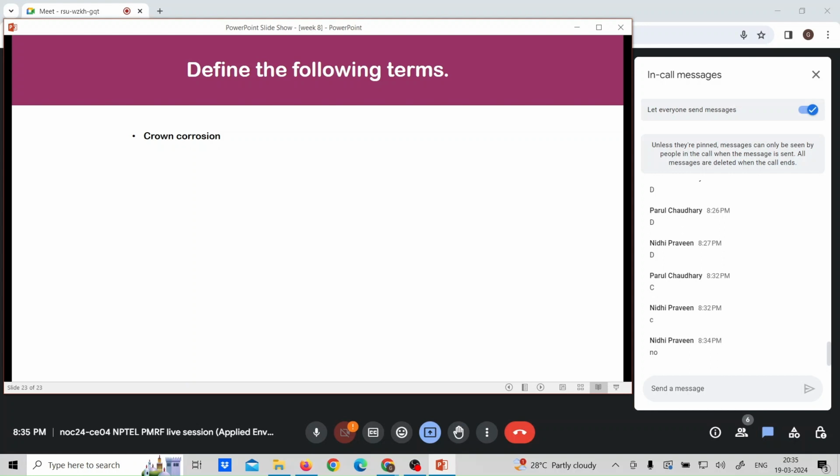So this H2S, hydrogen sulfide gas, is a corrosive gas. When this gas builds up, it is going to cause corrosion of the pipeline. Even if it's a concrete pipeline or something, there is going to be some corrosion in the top part of the pipeline.